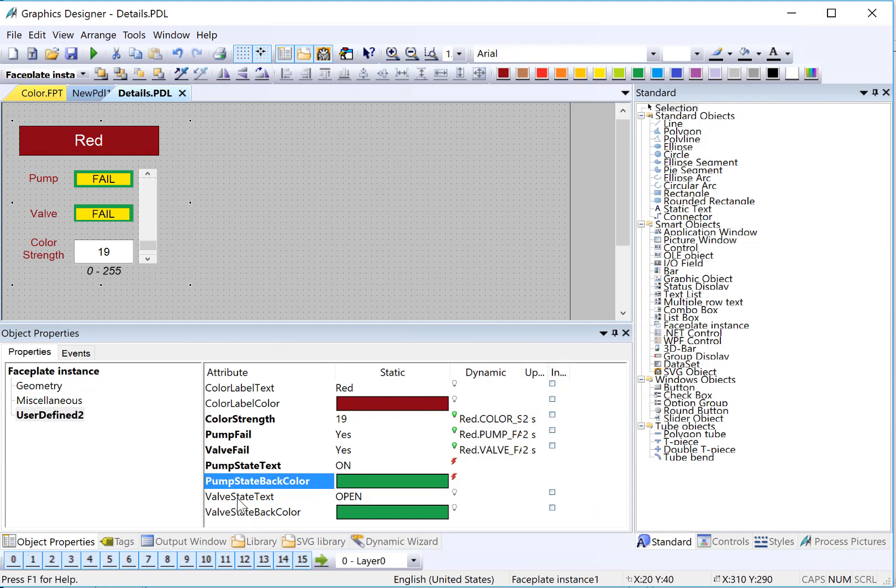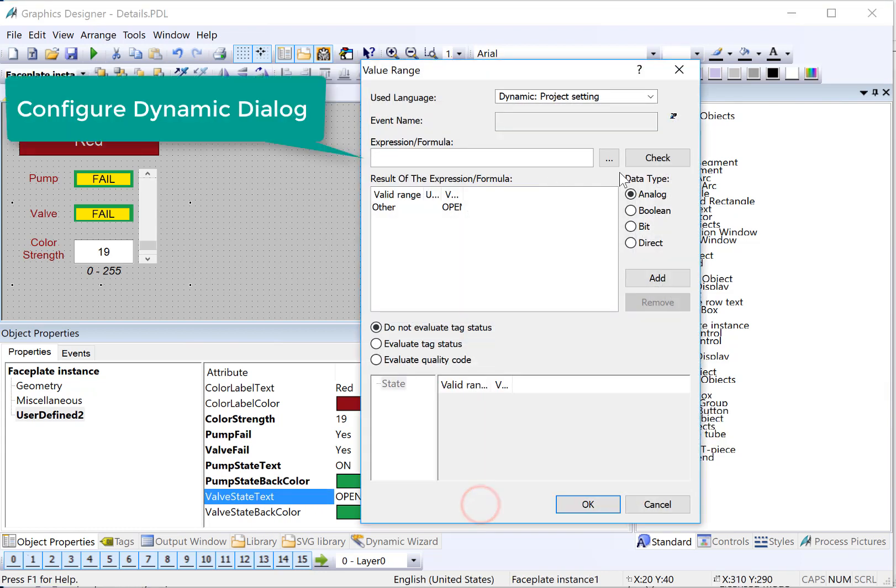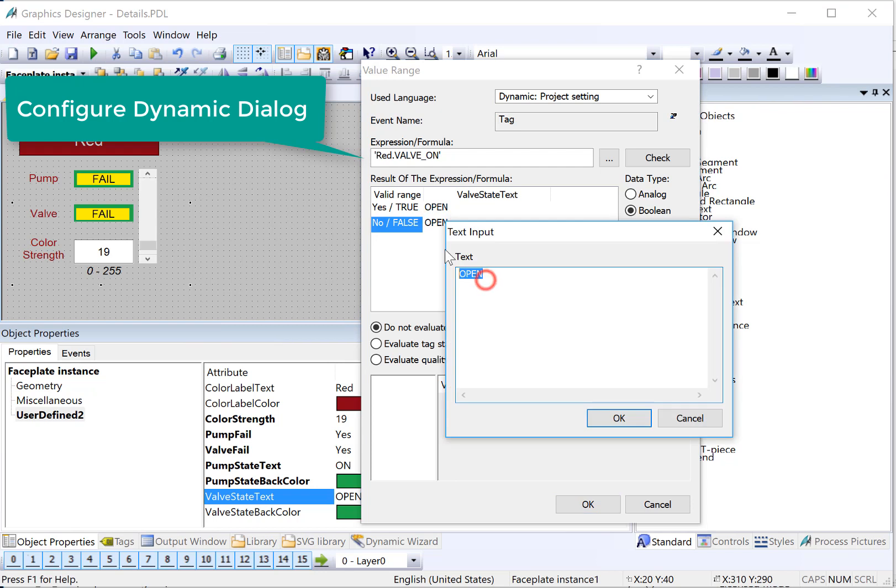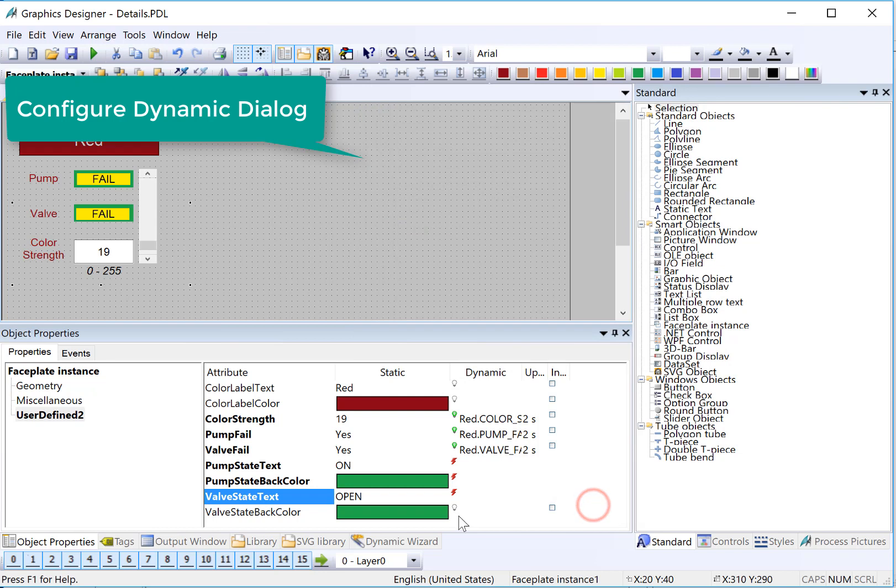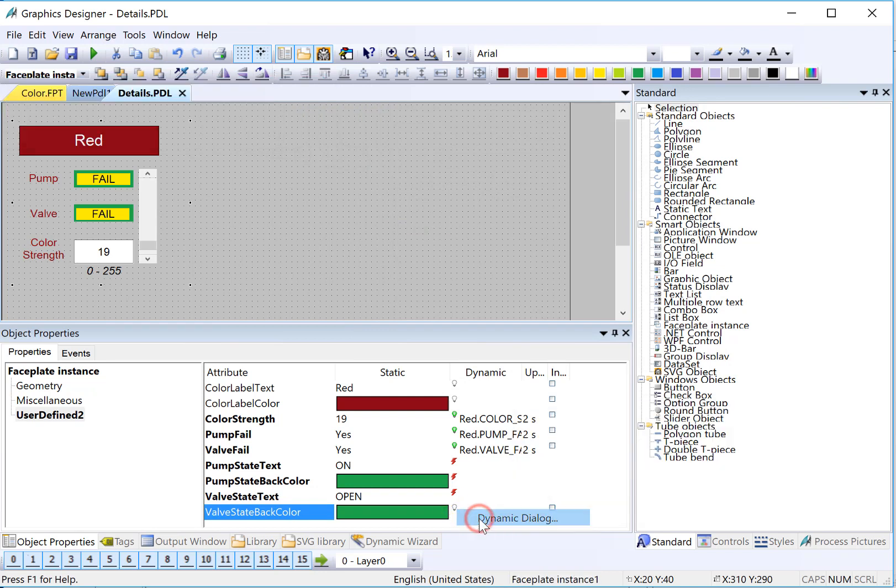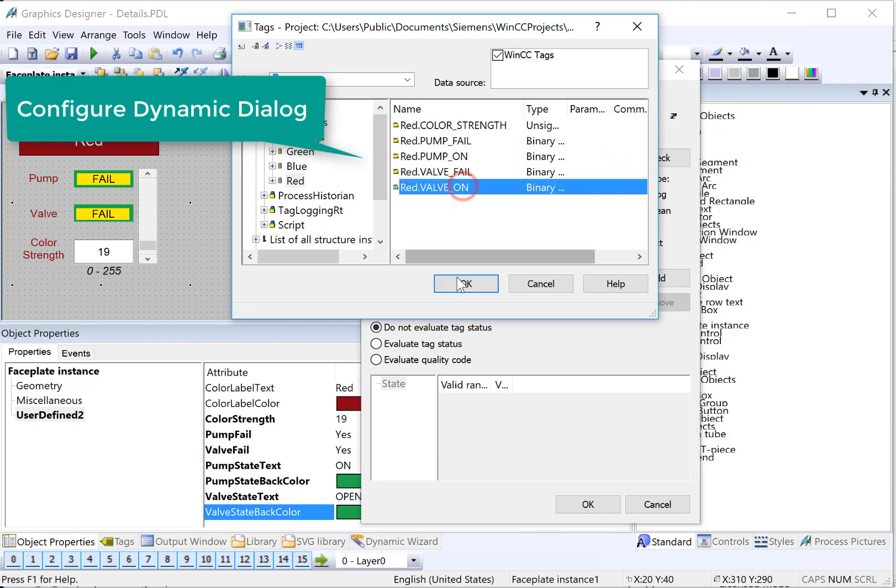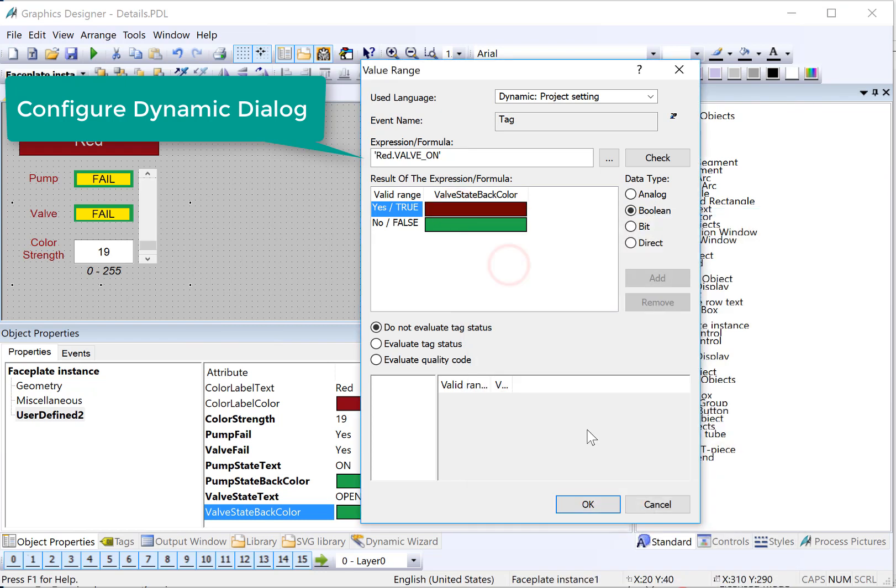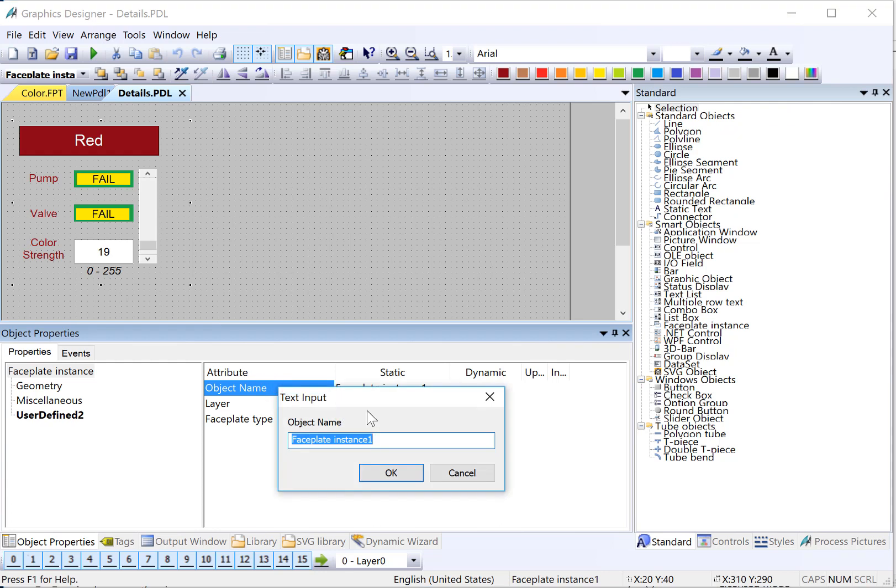We'll do the same thing for our valve state text and valve state color. Right-click, dynamic dialog, our valve state, boolean. And if it's on, then we'll say open. And if it's off, closed. And finally, right-click, dynamic dialog. This is for our background color. We'll look at our same tag, boolean. And then if it's open, it will be red. If it's closed, it will be green. And for this particular object, I'd like to change the name from object faceplate instance 1 to fp color red.